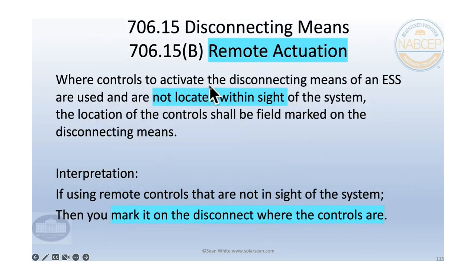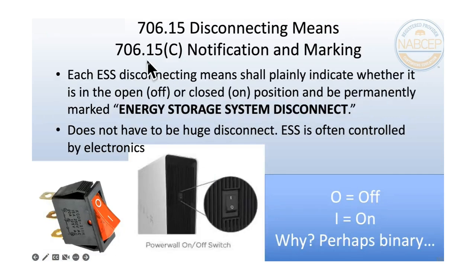So remote actuation, what we're talking about, where controls to activate the disconnecting means are used and are not located within sight of the system, the location of the control shall be marked on the disconnecting means. So if you're using remote controls that are not in sight of the system, then you mark on the disconnect where the controls are. But typically you're going to be able to disconnect it in both places. And so here we have some disconnecting means.